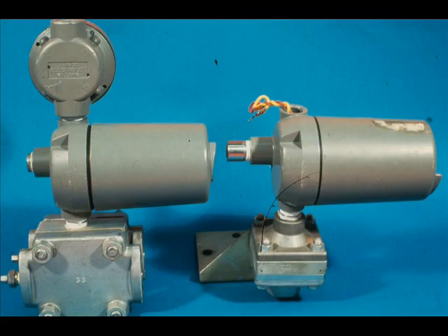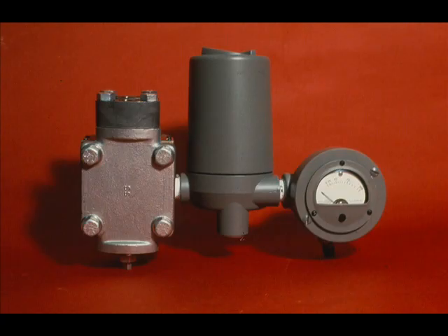The Honeywell models 411 and 412 are examples of strain gauge type differential pressure and pressure transmitters. The model 411 will convert differential pressures to 4 to 20 milliamps DC. It is referred to as a delta P to I transmitter.